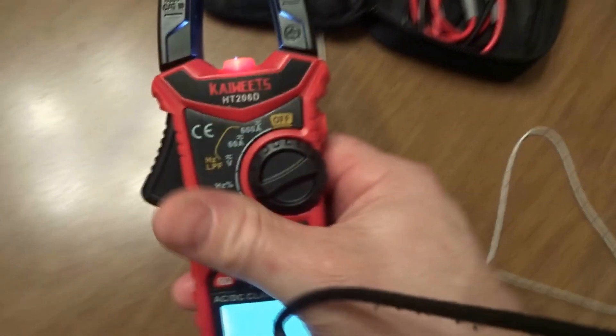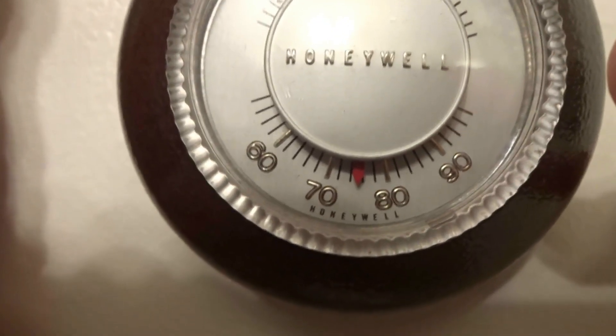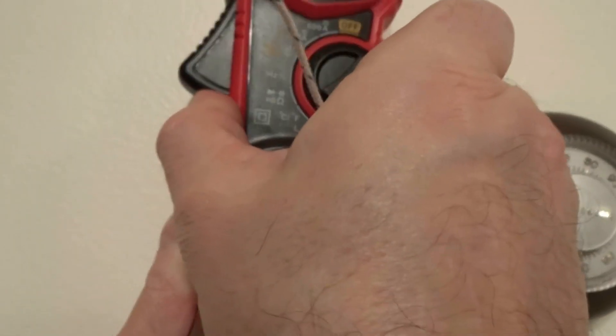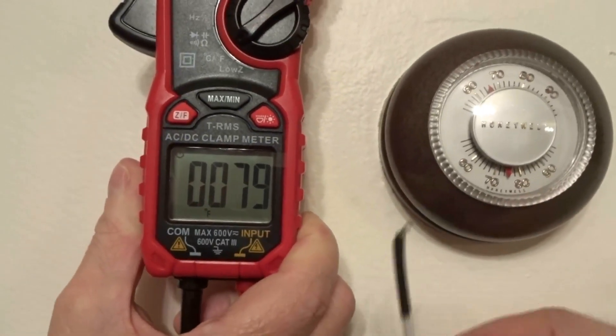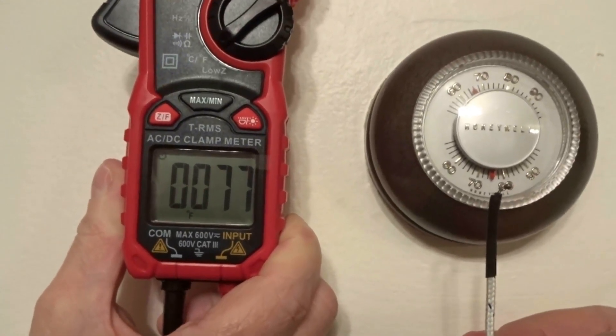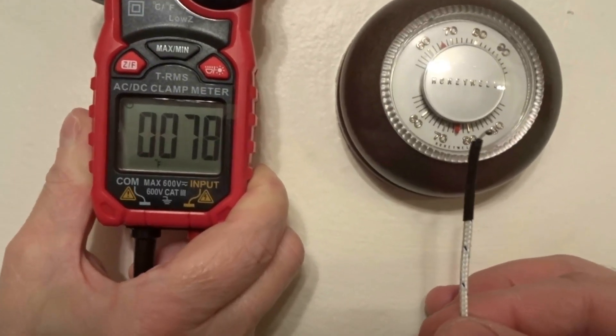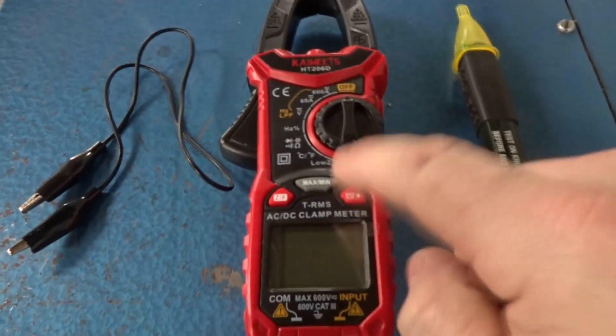Let's take this over to the thermostat. The lights have been on in here so it's going to affect this, but you can see it's reading about 75-76 degrees. If we switch to Fahrenheit and hold the probe anywhere here, it's reading 77 degrees. So it's very accurate, and that's a good way to test if your thermostat is actually reading correctly.